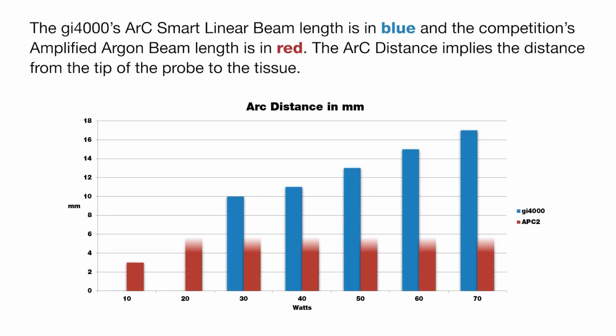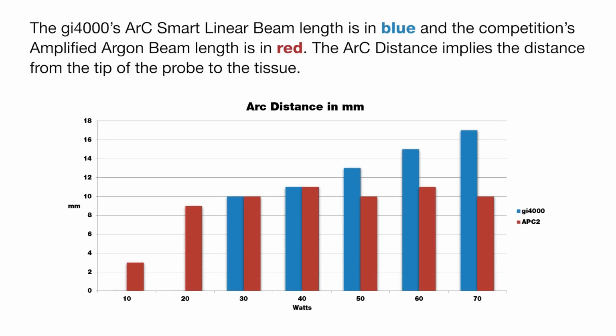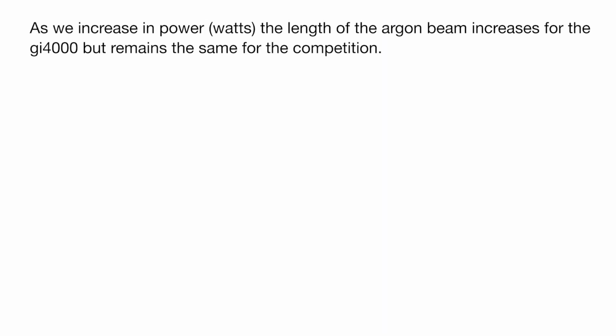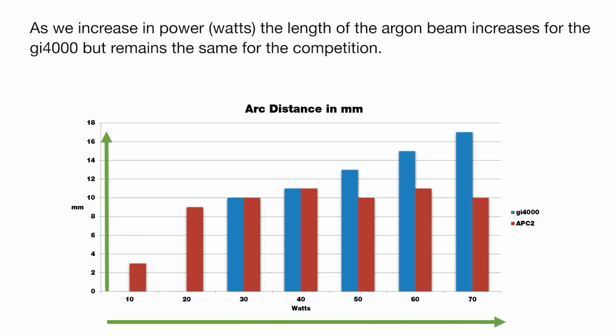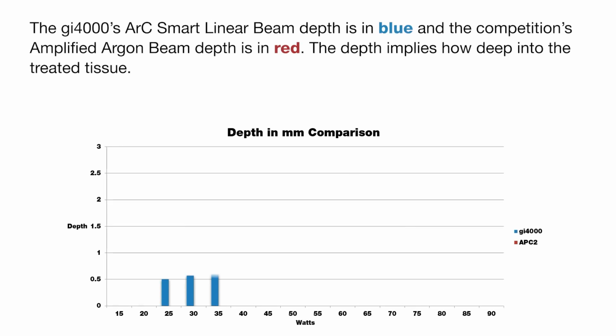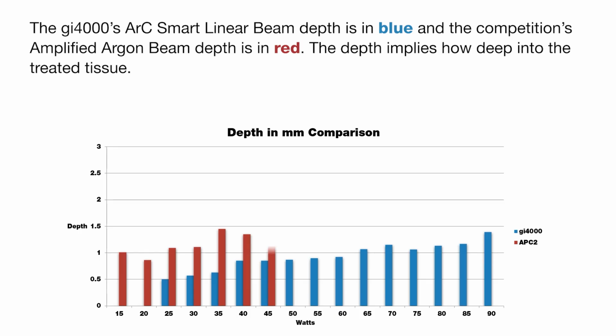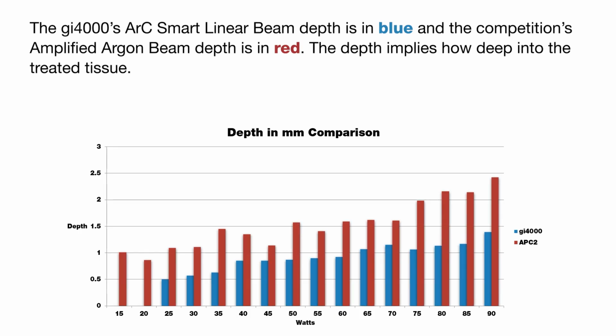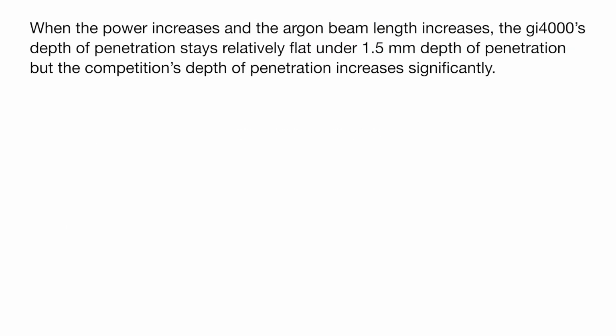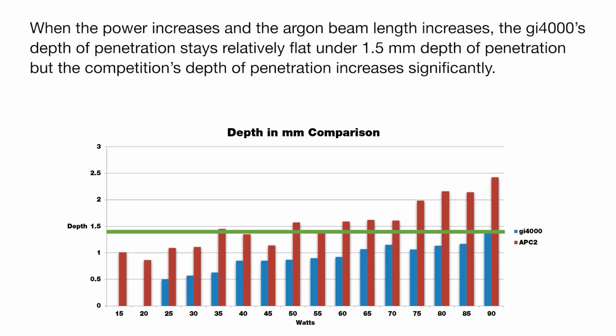As we increase in power, or watts, the length of the Argon beam increases for the gi4000, but remains the same for the competition. The gi4000's ArcSmart linear Argon beam length is in blue, and the competition's amplified Argon beam length is in red. The arc distance implies the distance from the tip of the probe to the tissue. The competition's Argon beam increases minimally when the power is increased.